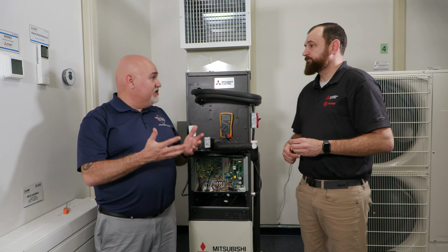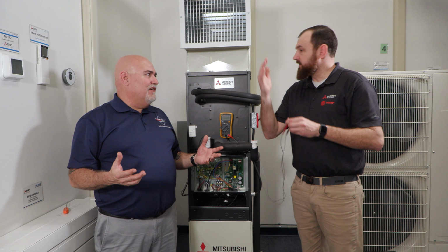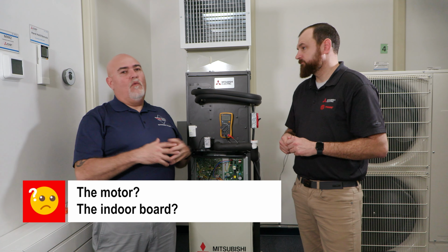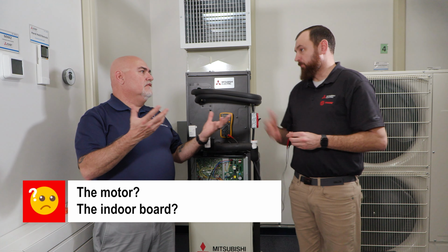Did it blow a fuse on the board? Right. We got to look at these basic things and rule them out. Is the motor caked with dirt? Is it completely covered in dirt? Hitting the housing or something? It's hitting the housing. Maybe somebody took the blower wheel out for maintenance. They put it back, but they didn't tighten the set screw, and now it's shifted over, and now it's locked up and it can't spin. Now we've ruled all that out. So now we have to figure out one of 2 things. Is it the motor, or is it the indoor board?